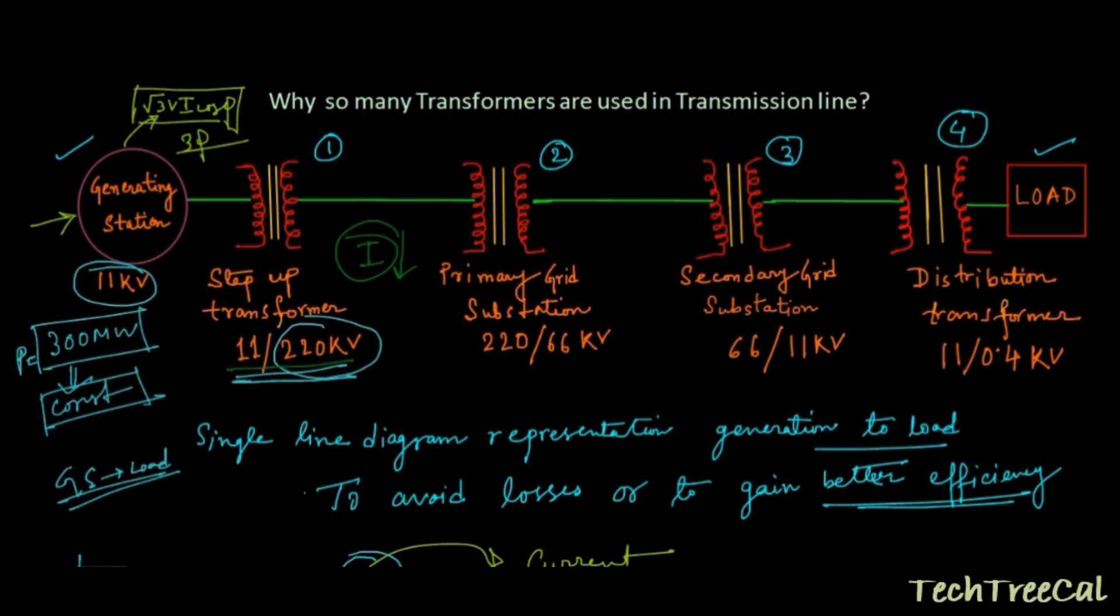So here the voltage is stepped up to 220 kV. Then after transmitting a long distance—it is generally a long distance transmission—it is stepping down to 66 kV. Again at secondary grid substation it is decreased to 11 kV, and then from the distribution transformer it is stepping down to 400 volt and supplied to the load.